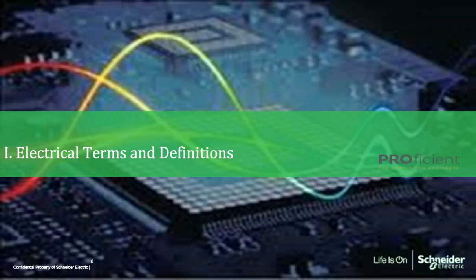So the first three basic terms that I'd like to cover are the following, which are typically used when discussing AC power and harmonics. First one is real power, which is the power that does the work. It is required by all applications and is supplied by the power source. The second one, and one that we'll focus largely on today, is reactive power. It is the power that is sometimes required by applications. An example would be AC motors, to permit real work to be done. Many times, as in AC motors, inductive reactive power is required to create the electrical field that permits the real work to be done. And then lastly, apparent power, which is the root mean square of the real power and reactive power.